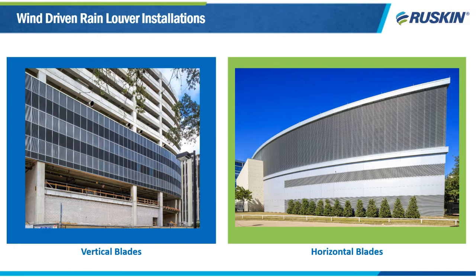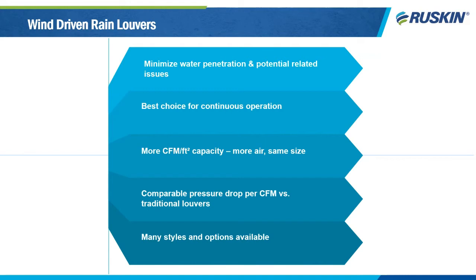So to recap, wind-driven rain louvers are the best choice for outside air intakes. They keep rain out of the building and minimize the problems of water coming in, such as damage to the building and mold growth. Because they reject so much rain and they have somewhat low pressure drop, they are the perfect choice for airflow systems that are pulling high intake velocities and long intake periods.